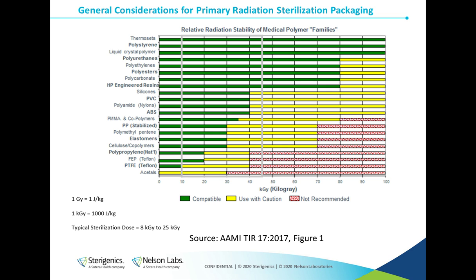You can see I put a gray box around the range of typical sterilization doses from about 10 to 45 kilograys. The materials that are green across that entire range tend to be very easy to use in radiation sterilization and are good candidates for primary sterilization packaging. Things like polyurethanes, polystyrene, polyesters are very resistant to radiation, whereas polypropylene and PTFE, polytetrafluoroethylene, may have issues. Though there are stabilizers that can be used for things like polypropylene that can make it work quite well in radiation sterilization. The point is to be aware of the radiation impact for the material you propose to use for sterilization packaging.